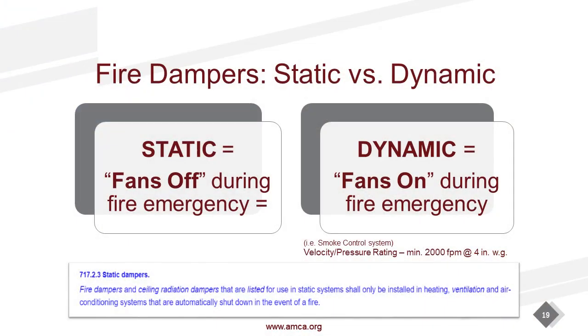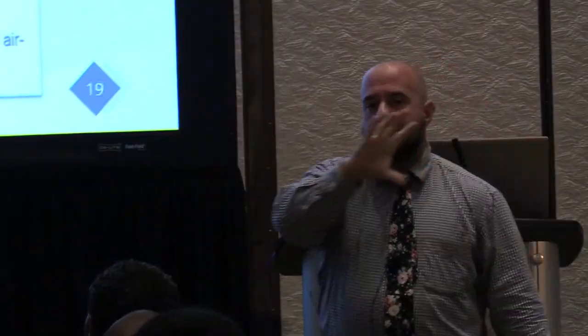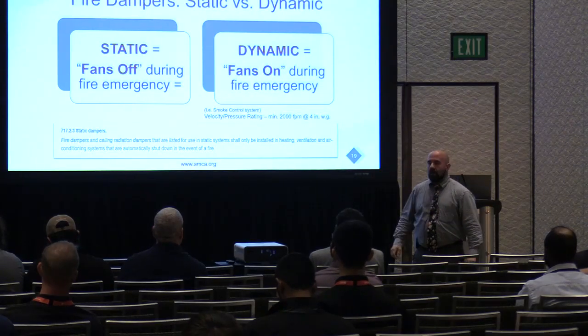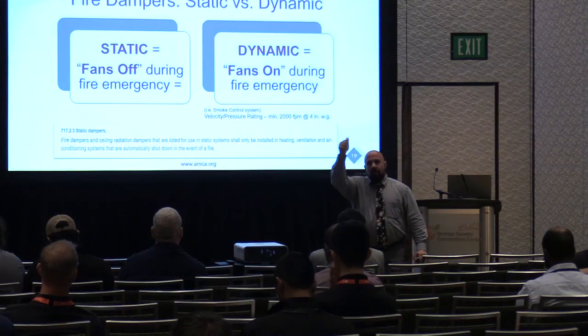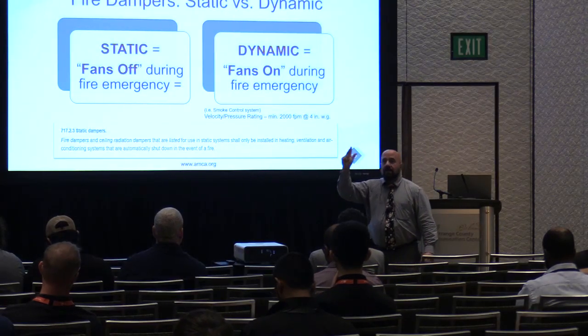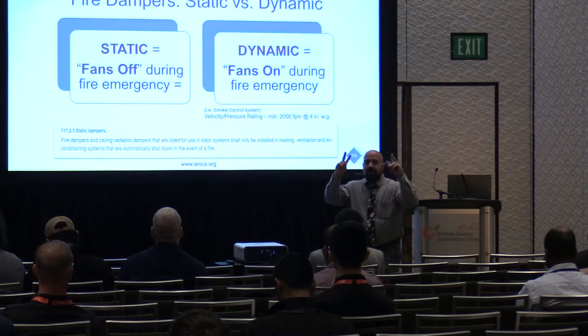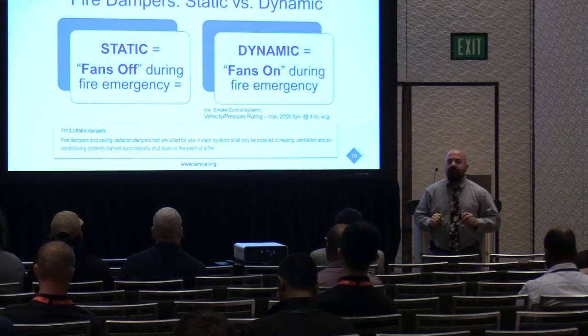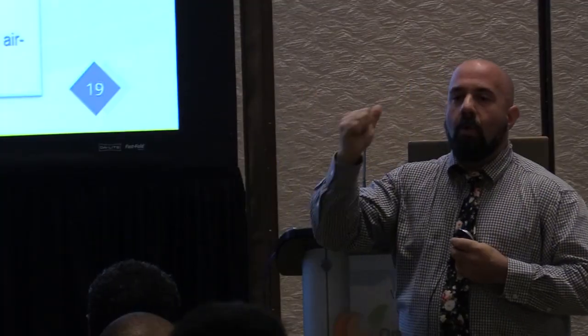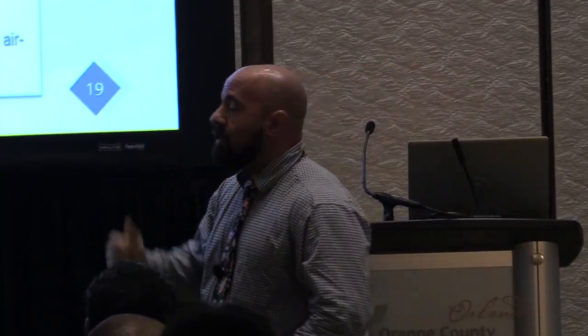So when we talk about the system, is it static or dynamic? The building code states fire dampers and ceiling radiation dampers that are listed for use in static systems shall only be installed in HVAC systems that are automatically shut down in the event of a fire. So my fire damper does not have to overcome velocity and pressure or airflow moving through the ductwork. It's what we call still air. So maybe a smoke detector, a fire alarm panel, something in your design says, turn my units off. My dampers do not have to overcome those forces. That is considered static. The specification for that fire damper will not include a pressure or velocity rating because it has not been tested for either.